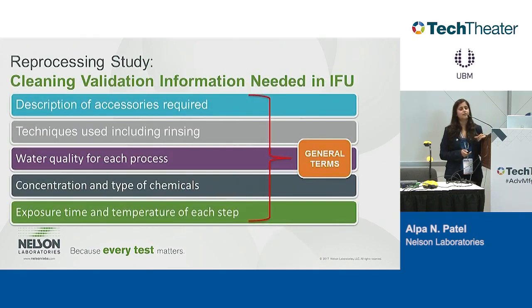Some of the information that should be in an IFU are listed out here. Now, how specific do you have to be? I had a call from one of our clients saying the healthcare facility won't process our device in an automated washer because we have specified to use deionized water as the final rinse. And they don't have deionized water.